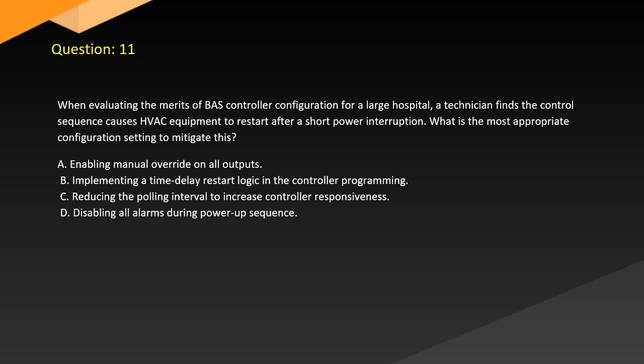Question 11. When evaluating the merits of BAS controller configuration for a large hospital, a technician finds the control sequence causes HVAC equipment to restart after a short power interruption. What is the most appropriate configuration setting to mitigate this? A. Enabling manual override on all outputs. B. Implementing a time delay restart logic in the controller programming. C. Reducing the polling interval to increase controller responsiveness. D. Disabling all alarms during power-up sequence.